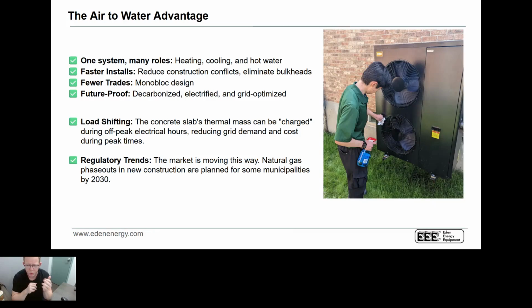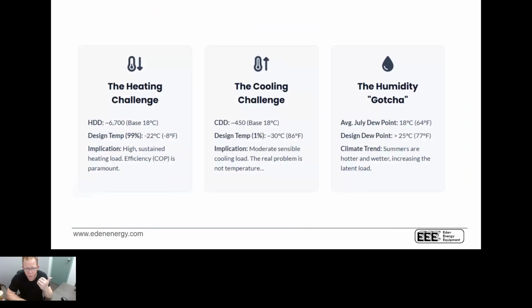We're going to talk through some real world research and how we can do that without getting crazy, without over engineering and making the system super complicated. The other advantage that obviously the air to water has is what I said from the beginning. Traditionally, we're doing boilers and some sort of forced air cooling. The beauty of it is with the regulatory trends driving us to get away from natural gas, it means that we can use the air to water heat pump for doing heating, cooling, and hot water. It's a fully electrified system. And when we design it right, we can have a really, really high system COP. So I want to talk through some of the different scenarios we can do.